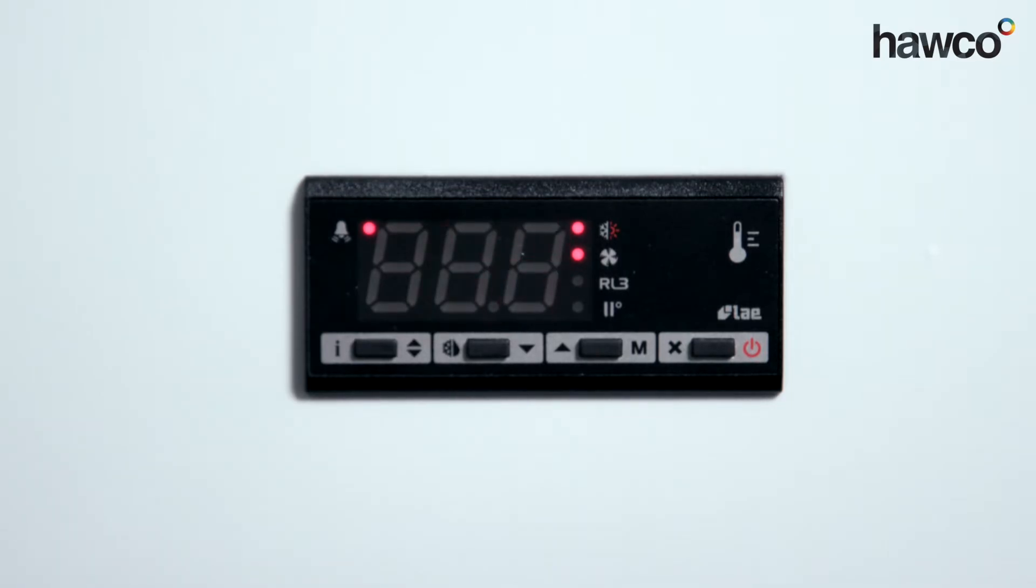When it comes out of the box, it's defaulted to two probes. It can be used for a defrost probe and there's a room probe as well. We've only got one probe set up, so it automatically comes up with an E2 error saying that you cannot see the second probe.